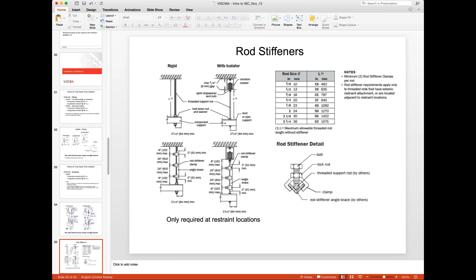And the notes on that table are also important: a minimum of 2 rod stiffener clamps. It's rare, but occasionally you'll see just one piece of angle bolted to the side of that rod that doesn't shorten the effective length of the rod. The purpose of those stiffening clamps and attachments is to effectively shorten the unsupported length of the rod, so when you do your buckling calculation, depending on your variables, typically like an L sub U, you can now use what's shown in that drawing, say a 24-inch instead of the full length of the rod, which dramatically increases your buckling allowable on these rods.